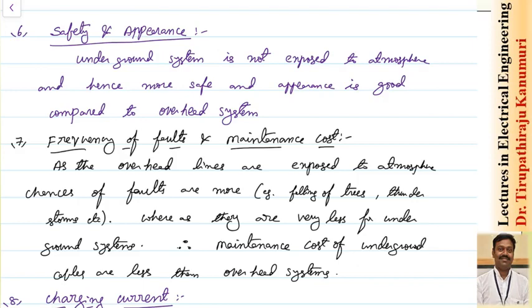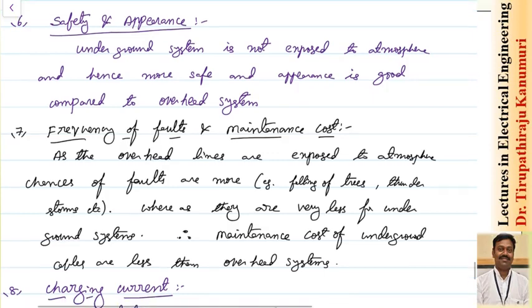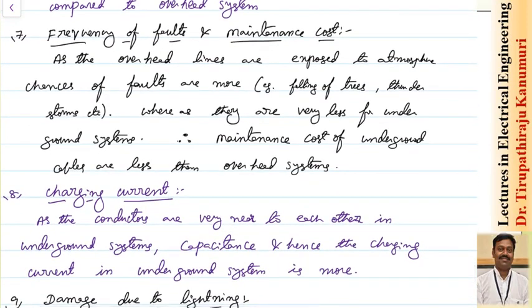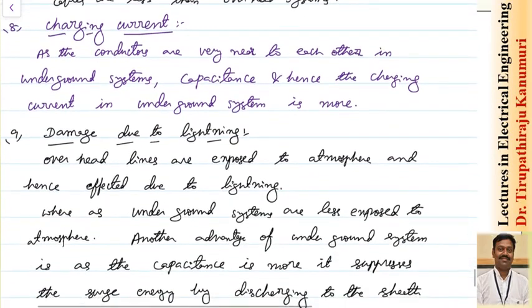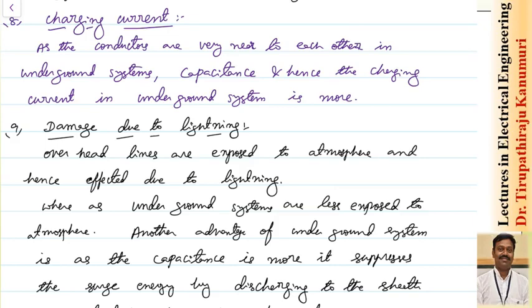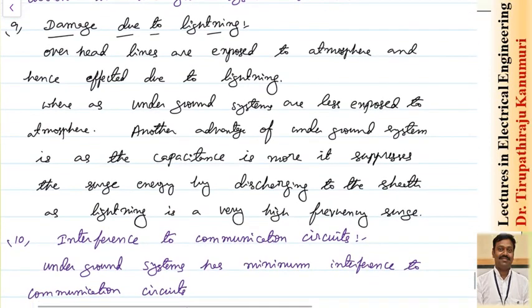Now the advantages of underground cables: safety and appearance are very good because they are not exposed to the atmosphere — no person will touch them and get a shock, and the appearance is neat. Regarding maintenance cost, overhead lines exposed to the atmosphere have more chances of faults like falling trees and thunderstorms, whereas these are very less in underground systems, so maintenance cost of underground cables is much less.